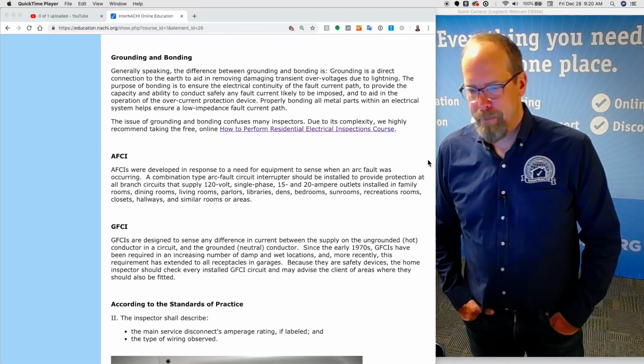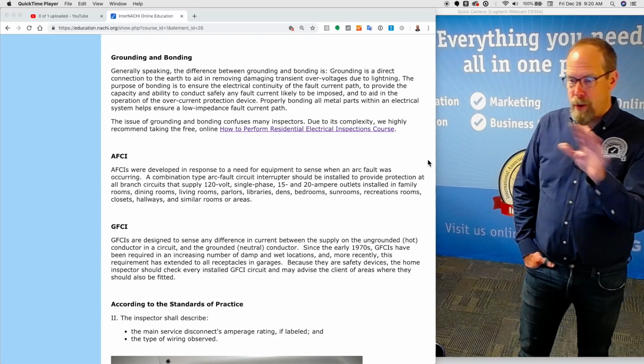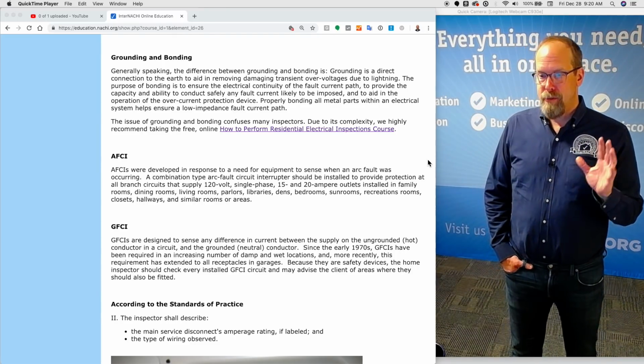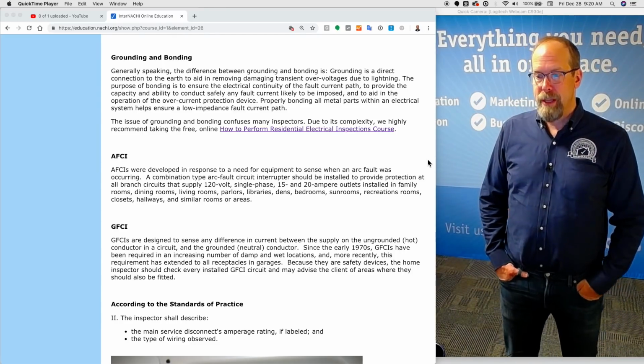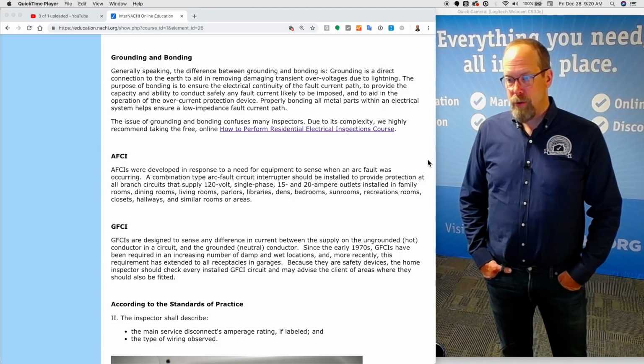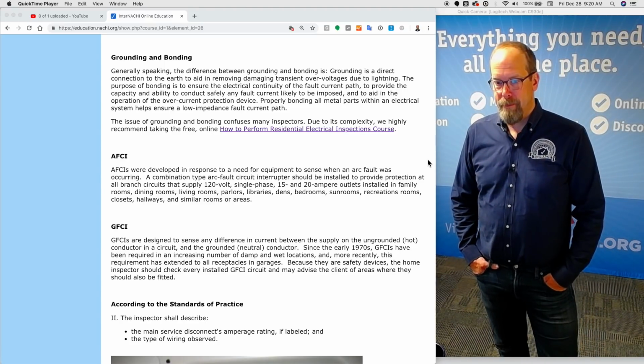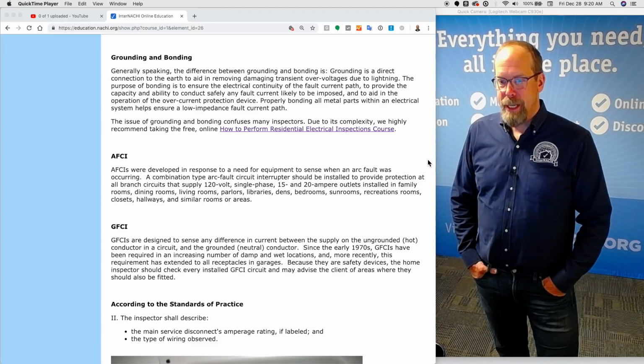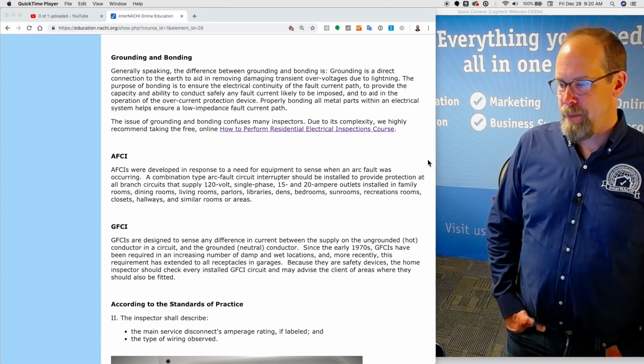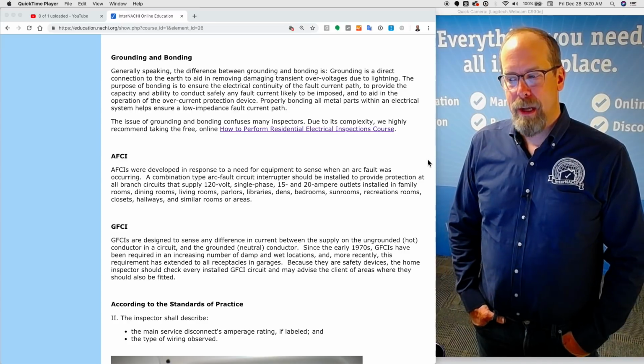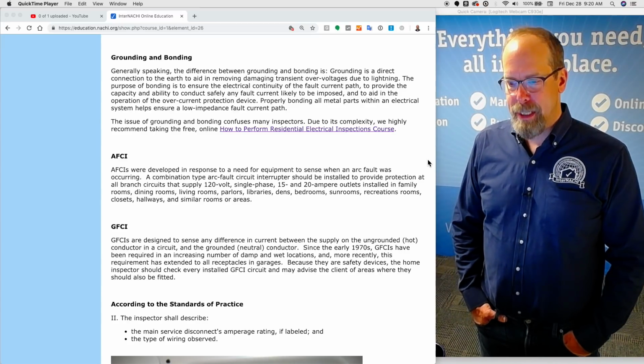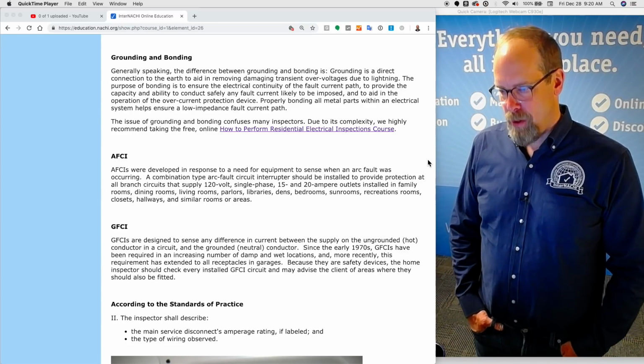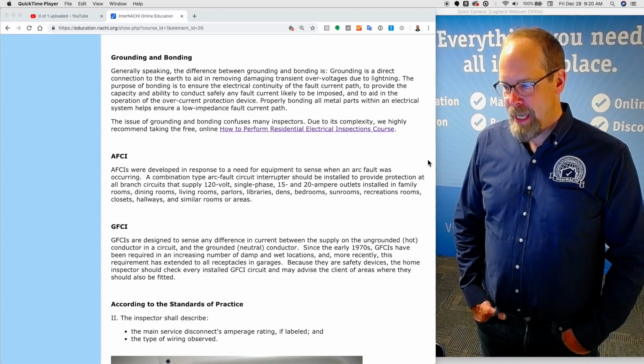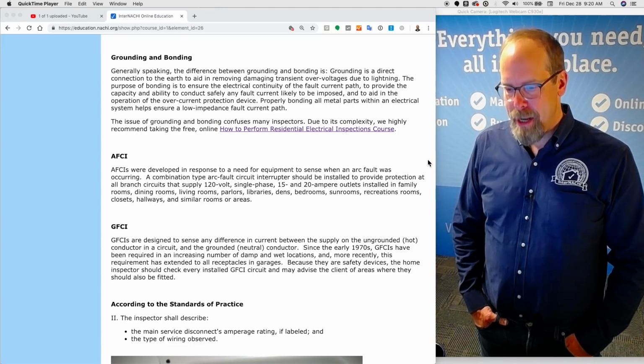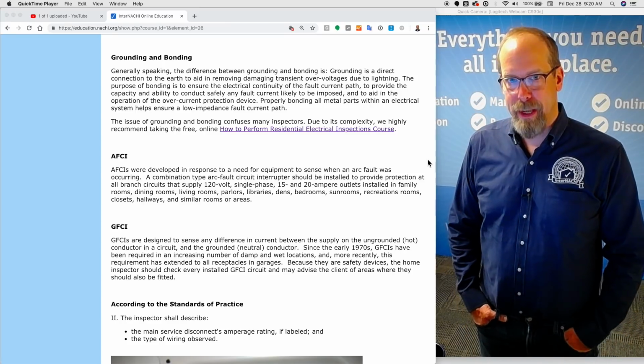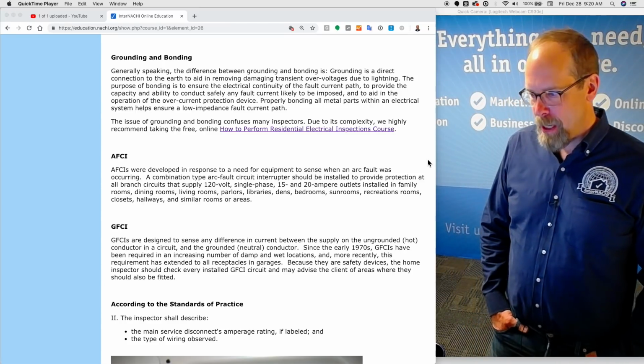Grounding and bonding. Generally speaking, the difference between grounding and bonding is grounding is the direct connection to earth to aid in removing damaging transient overvoltages due to lightning. And the purpose of bonding is to ensure the electrical continuity of the fault current path, to provide the capacity and ability to conduct safely any fault current likely to be imposed, and to aid in the operation of the overcurrent protection device. So that's what grounding and bonding is.